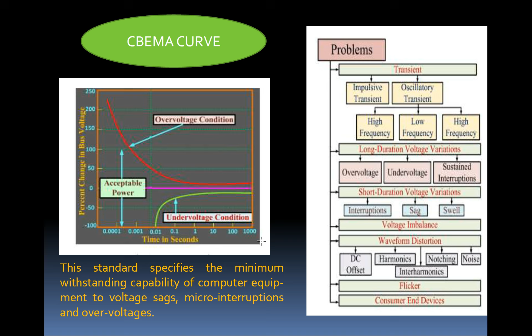How do we evaluate a power quality problem? First, we need to identify the problem category. Is it flicker? Is it voltage? Is it transient? Is it harmonics? And then we characterize each of these problems. Is it impacting our equipment? It can be a breakdown. Maybe our molding equipment breakdown is due to these harmonics. For example, I was assigned a project at Port Johor, Tanjung Pelepas Port, where they had downs in the system due to voltage sags. They did not know the origins or the causes, but they knew the characteristics.